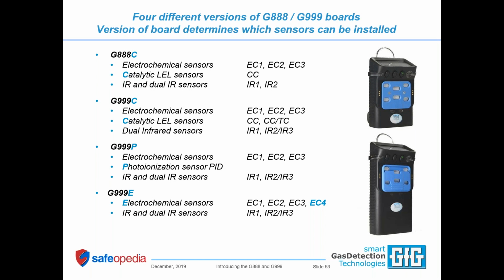With the 999C, you support the catalytic sensor, the IR sensors, and all of the electrochemical sensors. It does not support PID. If you want PID, we are going to sell you a G999P. The P board has a dedicated position for the PID sensor. We use IR LEL to measure combustible gas, and it has the complete range of electrochemical sensors.